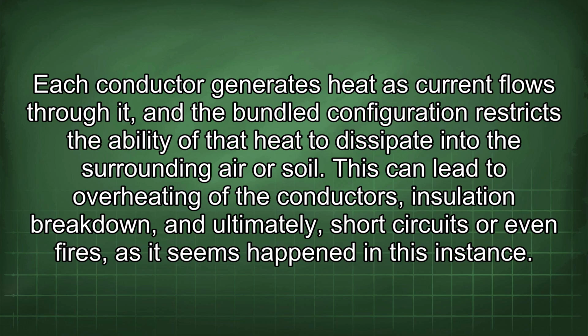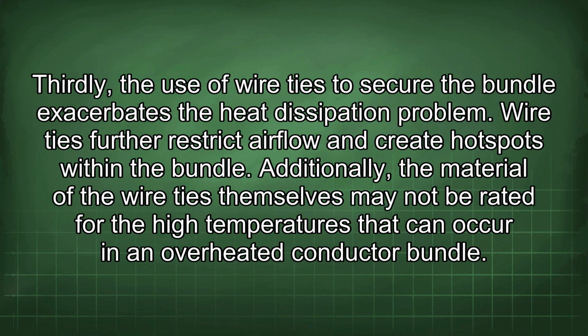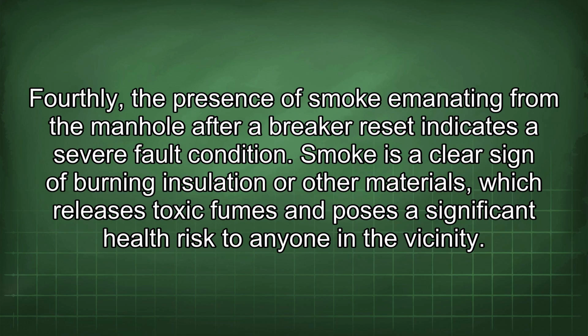happened in this instance. Thirdly, the use of wire ties to secure the bundle exacerbates the heat dissipation problem. Wire ties further restrict airflow and create hotspots within the bundle. Additionally, the material of the wire ties themselves may not be rated for the high temperatures that can occur in an overheated conductor bundle. Fourthly, the presence of smoke emanating from the manhole after a breaker reset indicates a severe fault condition. Smoke is a clear sign of burning insulation or other materials, which releases toxic fumes and poses a significant health risk to anyone in the vicinity.